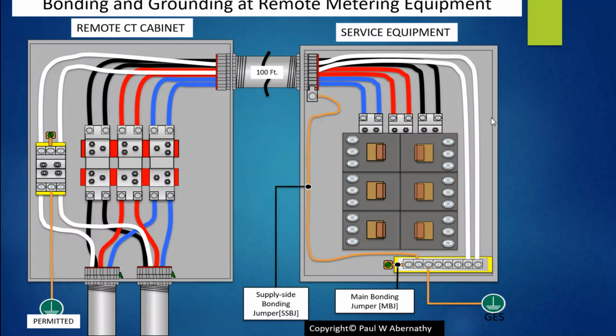Main bonding jumpers and panels are required to be of green finish. But here we're talking about something that's being utilized for a supply side bonding application. Now, here's how it's done. You've got regular standard lock nuts for the mechanical portion. Here I have a bushing with insulator in it because these are 4 and larger. So for abrasion, I've got that done. So this is the bonding that's taking place here.